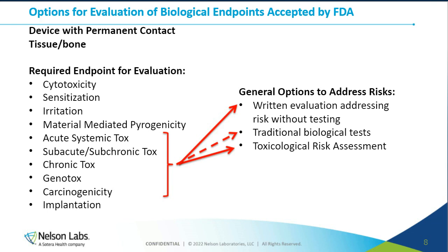For these things that are within the realm of systemic toxicities, you very clearly have three options. You often can do a written evaluation to address those without any testing at all, and we'll give an example of that. You still have the ability to do traditional biological tests. I would say carcinogenicity probably isn't a traditional biological test that you would do, though it still is an option. But we see people doing acute systemic and subacute subchronic tox along with genotox as their traditional biological tests, as opposed to a written evaluation or tox assessment.